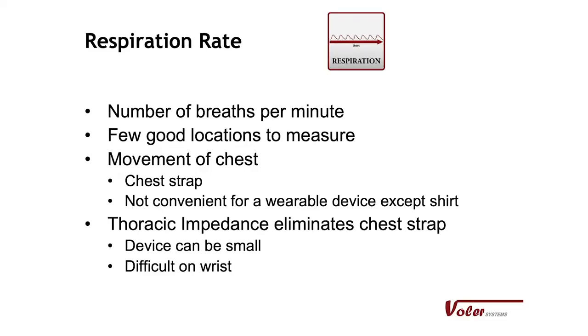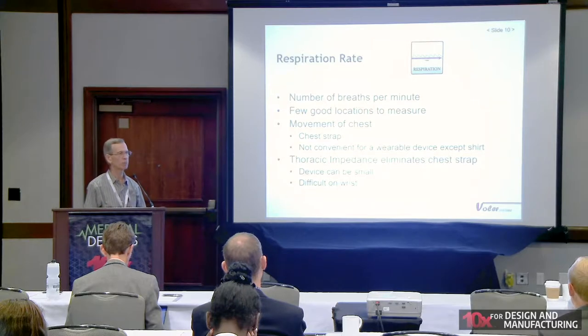Respiration is another very important parameter. The standard is a chest strap, which is easy to measure but inconvenient for a wearable device. Another approach is thoracic impedance — measuring the impedance of the chest as you breathe in and out, which changes and can be readily picked up. But this needs to be on the chest. People would like to put it on the wrist, but the wrist has a large impedance — your arm — between it and the chest, so that signal becomes much smaller and very difficult to use.